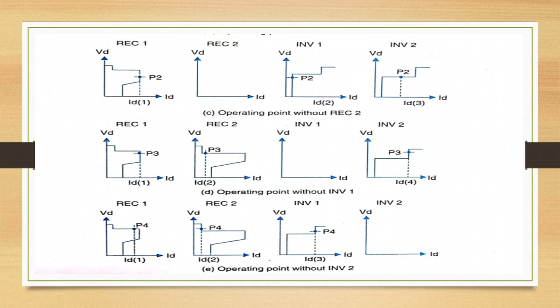The system can be shut down following a fault in a DC line or converter station and the faulted component isolated using high-speed disconnect switches, and this system can be restarted after adequate time for deionization of the arc path. System reliability considerations dictate the need for fast clearing of faults with minimum disturbance to the healthy parts of the system. DC breaker ratings can be minimized by utilizing the intervention of fast current controls in reducing the magnitude of the fault currents.